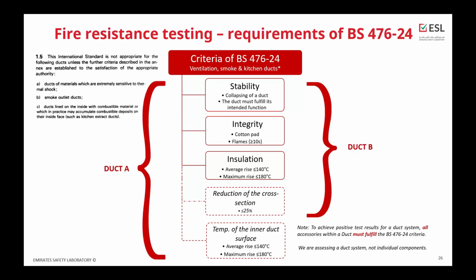So duct A needs to follow all of these criteria, and duct B only needs to fulfill 4 of them: insulation, integrity, stability, and cross-section reduction. If the duct system also contains accessories, you need to remember that to achieve positive test results for a duct system, all accessories within the duct must fulfill the same criteria as a duct, because we are assessing the duct system, not individual components of it.